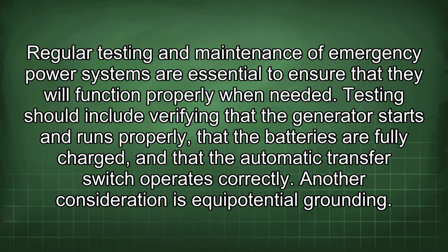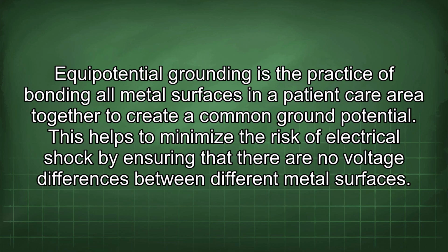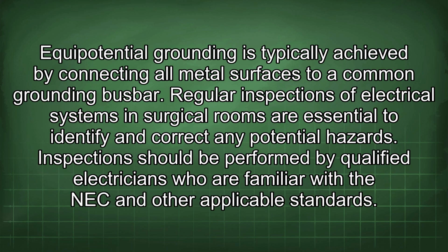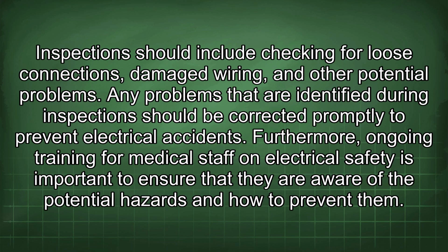Another consideration is equipotential grounding. Equipotential grounding is the practice of bonding all metal surfaces in a patient care area together to create a common ground potential. This helps to minimize the risk of electrical shock by ensuring that there are no voltage differences between different metal surfaces. Equipotential grounding is typically achieved by connecting all metal surfaces to a common grounding busbar. Regular inspections of electrical systems in surgical rooms are essential to identify and correct any potential hazard. Inspection should be performed by qualified electricians who are familiar with NEC and other applicable standards. Inspection should include checking for loose connections, damaged wiring, and other potential problems. Any problems that are identified during inspection should be corrected promptly to prevent electrical accidents.